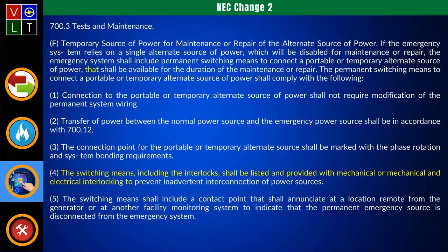Okay. All right. Now, this is 700.3(F). We're now in chapter 7, and this is where we get into the temporary source of power for maintenance or repair of the alternate source of power. They basically just did a revision here. The first one they did was in (4), and all they did was add some things. They added that the switching means, including interlocks, shall be listed and provided with mechanical and electrical interlocking to prevent what? Inadvertent interconnection of power sources.